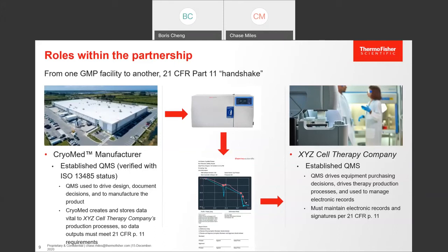However, the Cryomed manufacturer obviously makes the Cryomed product itself, right? That's obvious. However, the Cryomed itself, once it's at the XYZ cell therapy company, creates and stores data. Every time a run profile is initiated, a batch of cryo bags go in with a treatment, a profile is entered, you freeze those bags down, there's data that is generated with each event, from a user logging in to a user selecting a profile, the user running a profile, any alarm that might occur during a run for whatever reason that may be. All that information is stored in the Cryomed, and it's stored in a way that supports 21 CFR Part 11 requirements.